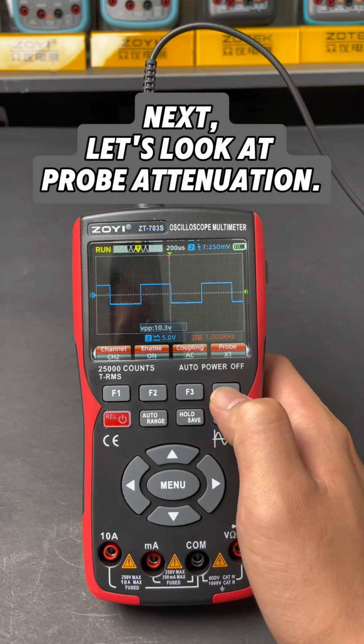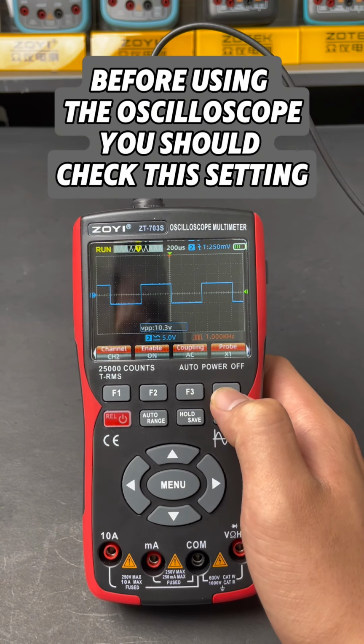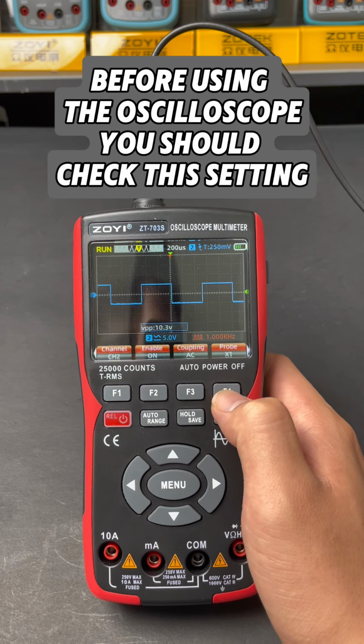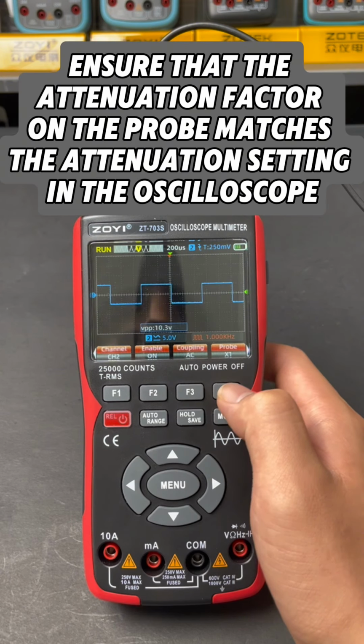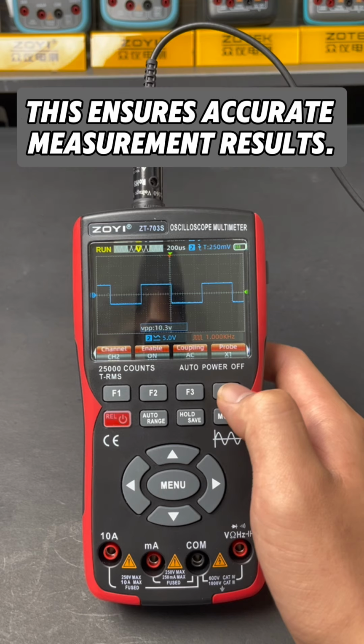Next, let's look at probe attenuation. Before using the oscilloscope, you should check this setting. Ensure that the attenuation factor on the probe matches the attenuation settings in the oscilloscope. This ensures accurate measurement results.